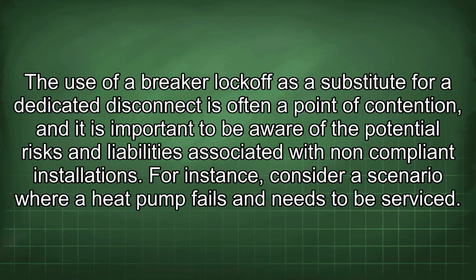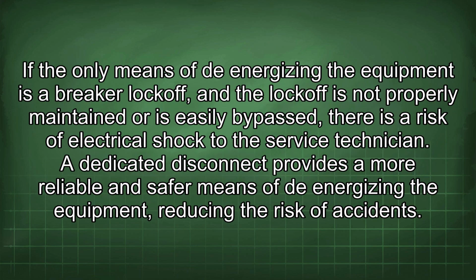The use of a breaker lockoff as a substitute for a dedicated disconnect is often a point of contention, and it is important to be aware of the potential risks and liabilities associated with non-compliant installations. For instance, consider a scenario where a heat pump fails and needs to be serviced. If the only means of de-energizing the equipment is a breaker lockoff, and the lockoff is not properly maintained or is easily bypassed, there is a risk of electrical shock to the service technician. A dedicated disconnect provides a more reliable and safer means of de-energizing the equipment, reducing the risk of accidents.